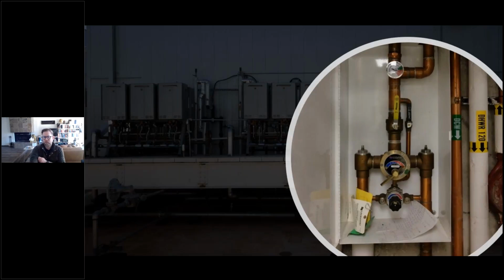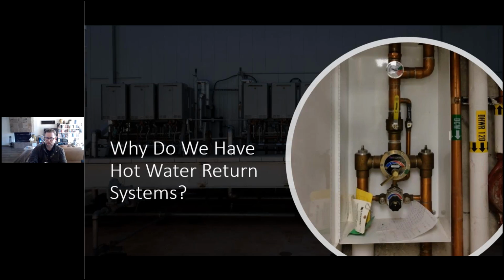Now, the question we should ask at this point is, why do we have hot water return systems? The reason is we are trying to bring that hot water source as close to the fixture as possible. Most codes have some kind of range, anywhere from 10 feet, or even less than that for public lavatories, all the way to 50 to 100 feet in some of the older codes, or a time of delivery. The reason for this is the longer you have to keep a fixture open and deliver hot water, that's water that we're wasting.